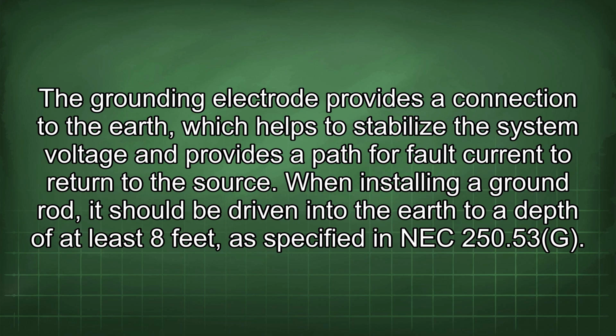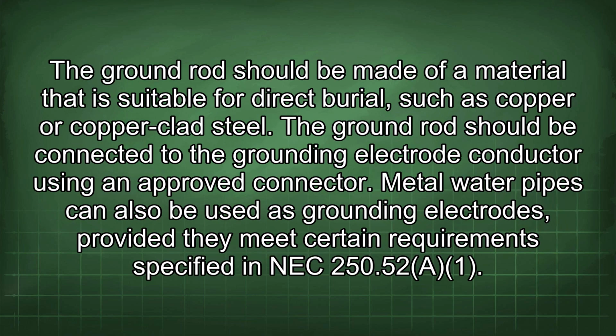When installing a ground rod, it should be driven into the earth to a depth of at least 8 feet, as specified in NEC 250.53 G. The ground rod should be made of a material that is suitable for direct burial, such as copper or copper-clad steel. The ground rod should be connected to the grounding electrode conductor using an approved connector.